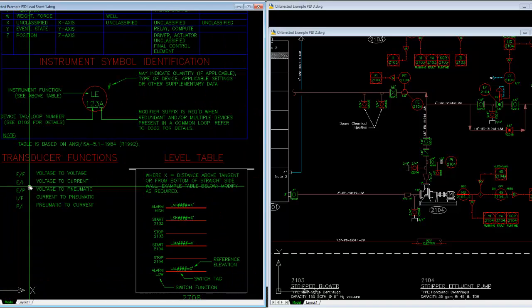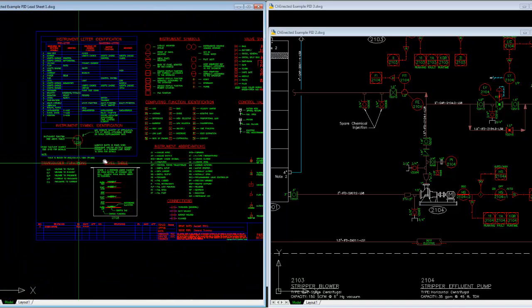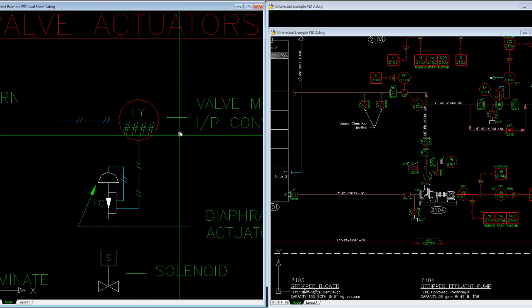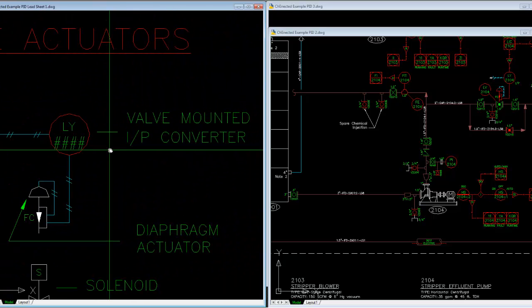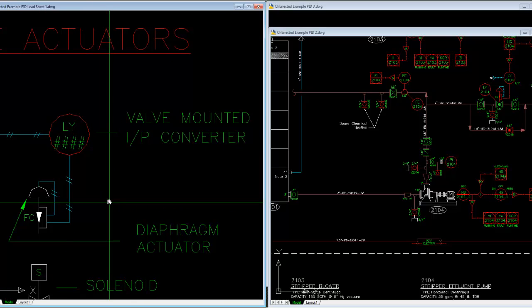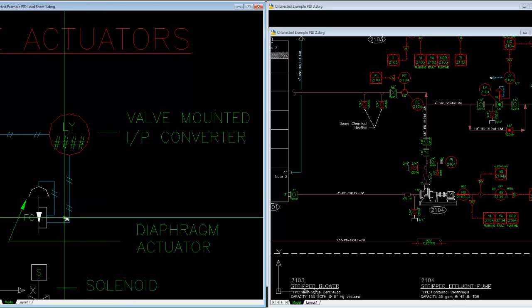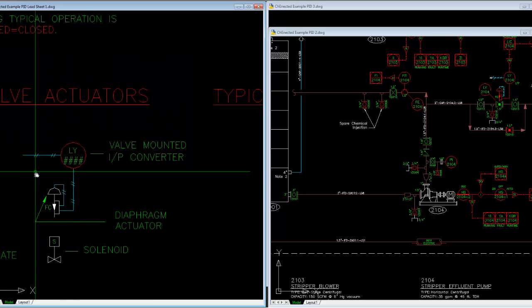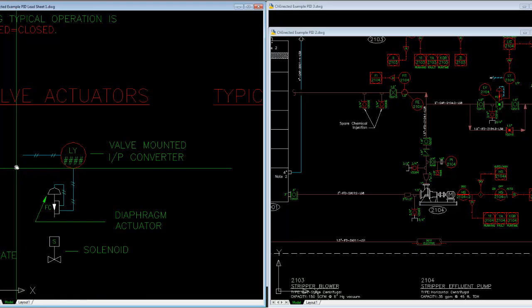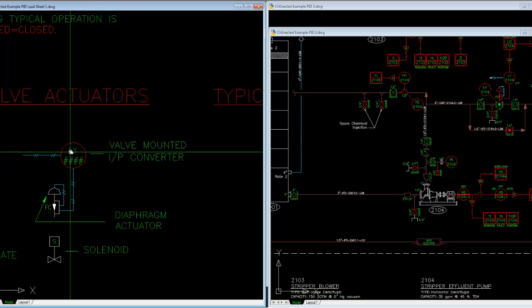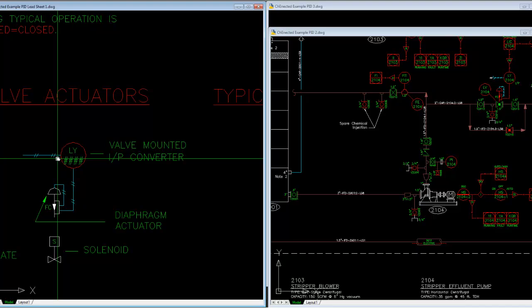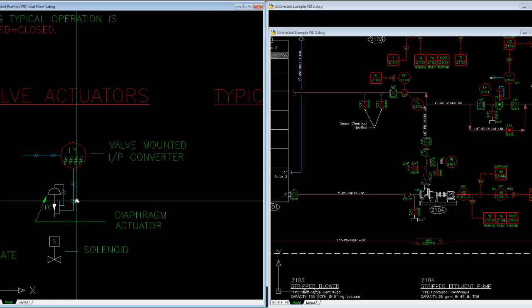The so-called transducer is something that's commonly applied on air actuated diaphragm valves that are modulating instead of open closing. In these cases, the device receives an electric signal that tells it position the valve to 40% open. The valve is actuated by air. So the transducer takes that electrical signal and converts it to an equivalent air output to drive the valve to a desired position.